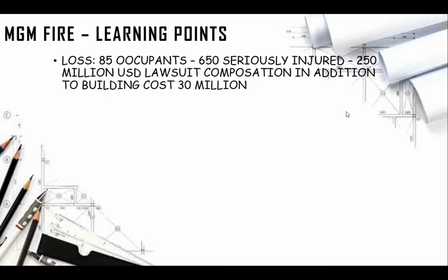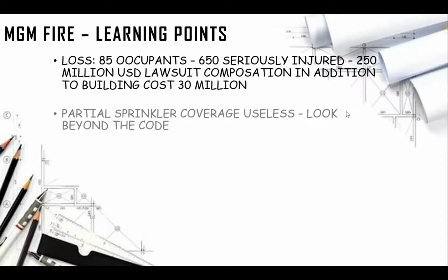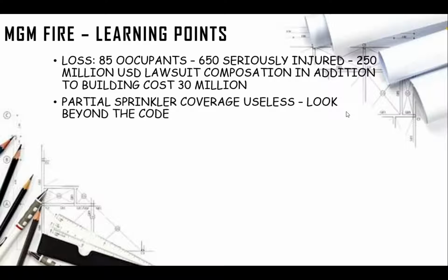So, what are the learning points from this MGM fire? It happened 40 years ago, and still it holds good. It left 85 occupants dead and 650 seriously injured. A 250 million USD lawsuit compensation was paid, in addition to the building cost of 30 million. And partial sprinkler coverage is useless. It is good for nothing. It is better not to have sprinklers than to have a partially sprinklered building. Because of the attitude, looking beyond the code did not happen there. As per the code, they provided sprinklers partially, and where the code did not require them, they didn't. But as a performance requirement, it is required. Now it is a lesson that we have learned from this.